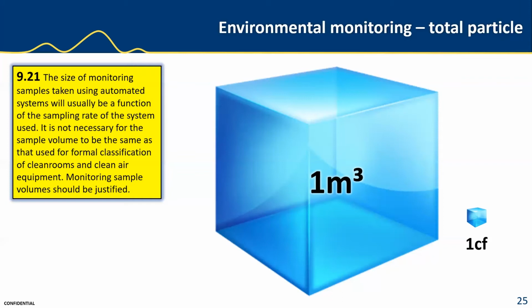And just for your information, the ratio of 1 cubic meter to 1 cubic foot is about 35.4. So a cubic foot is 35.4 times smaller than a cubic meter. So with a cubic meter, you need to take a lot more volume. But as it says in this section 921, the size of monitoring samples taken using the automated system, the continuous environmental system, is usually a function of the sample rate. And down around here, the remote particle counters are sampling at 1 cubic foot per minute.